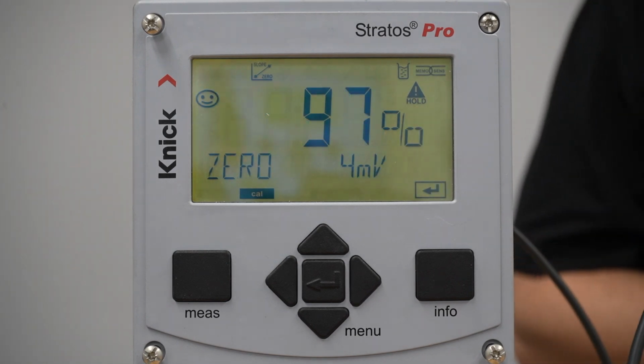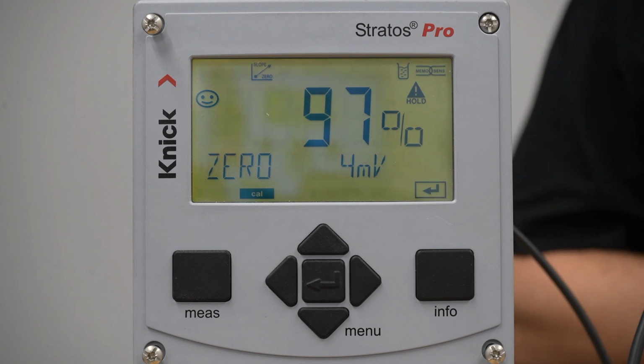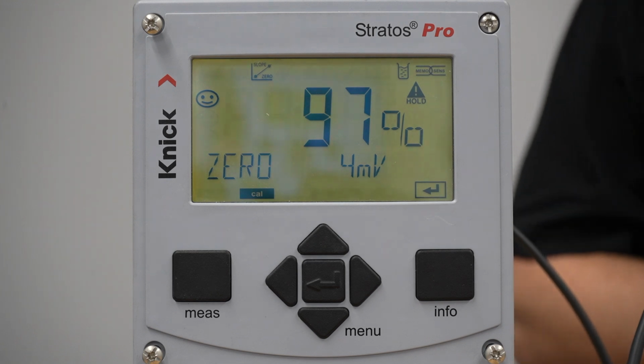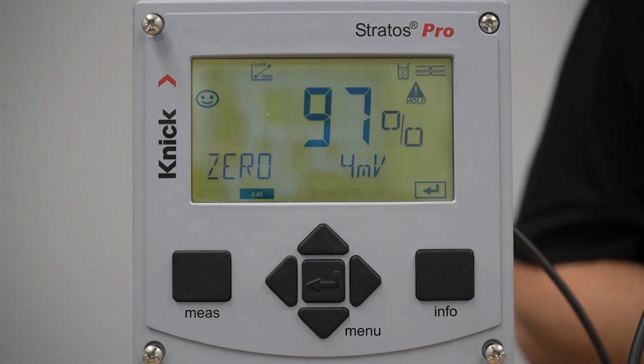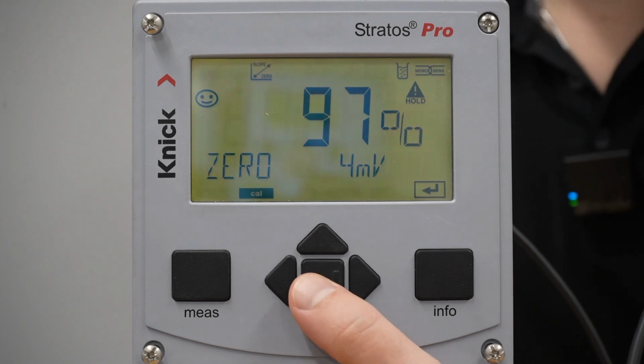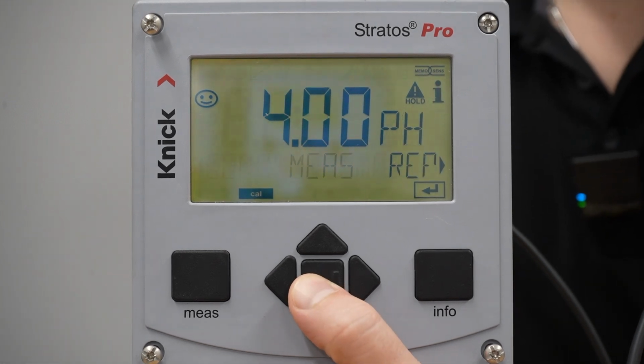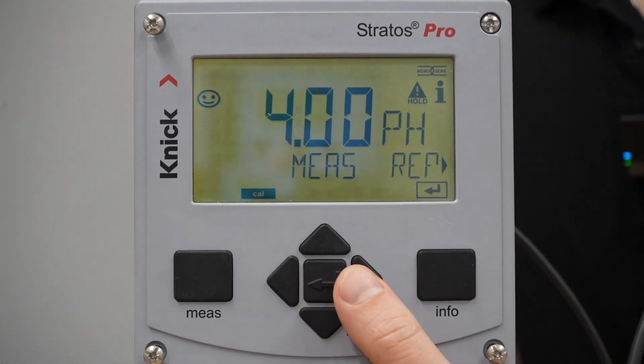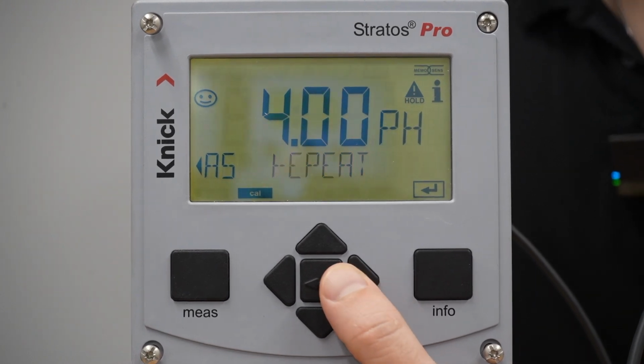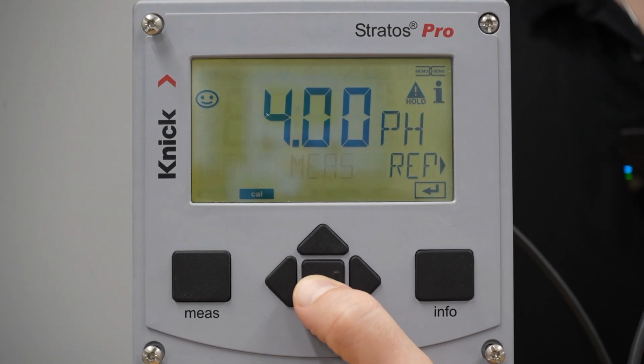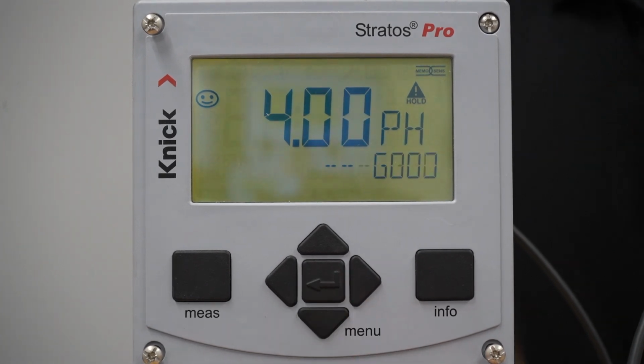Our calibration is now completed. We have a 97% slope with a 4 millivolt zero. I can come in here and select the enter button. Now I can either go back to measurement or select repeat if the calibration was not acceptable. I'll come in here and hit measure. It'll take us back to the measurement screen and we can move on to measure.